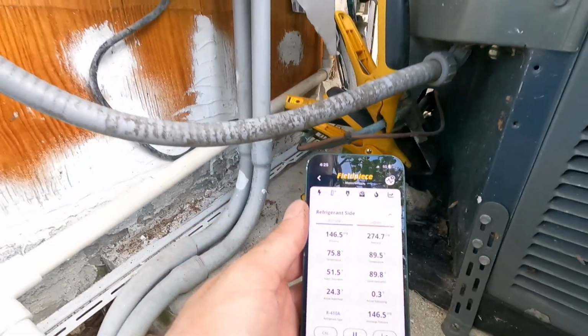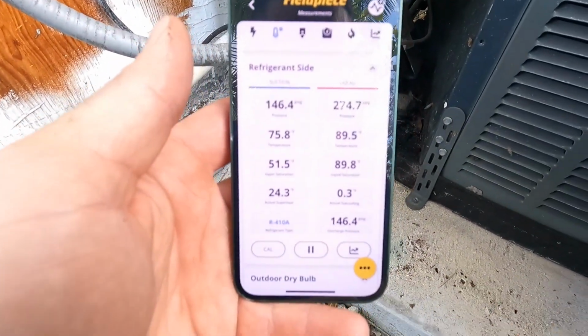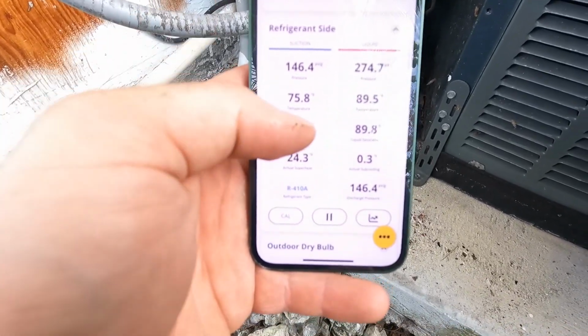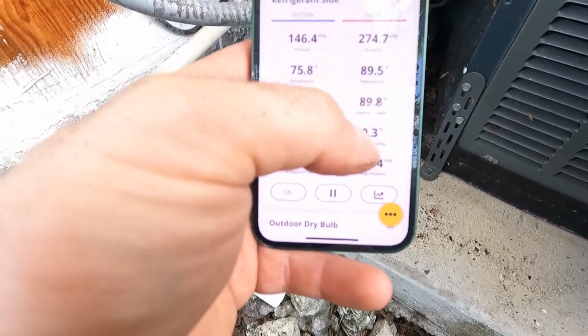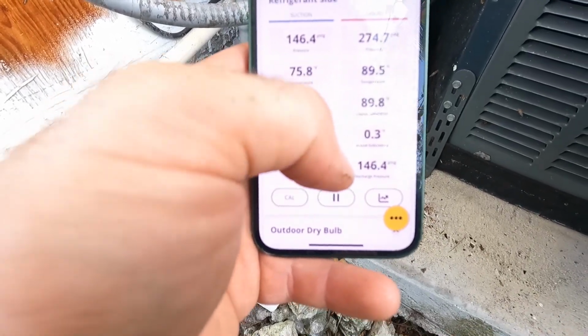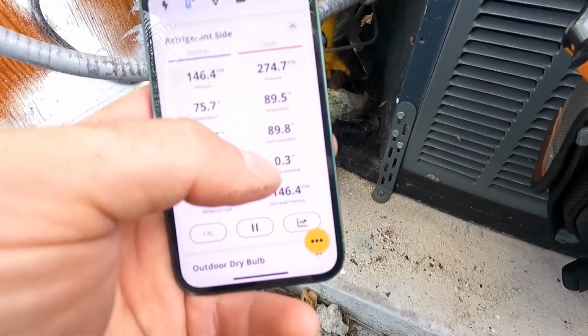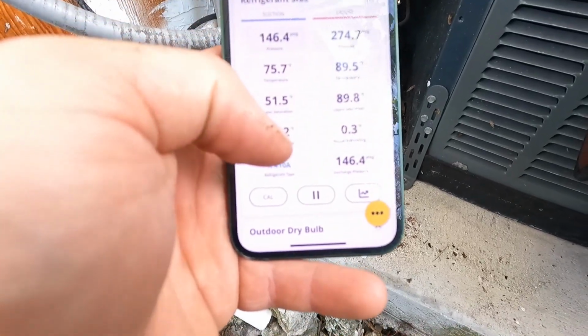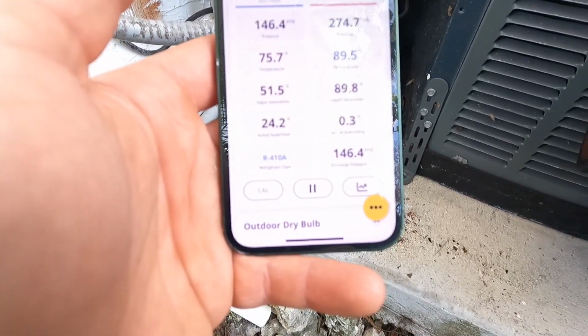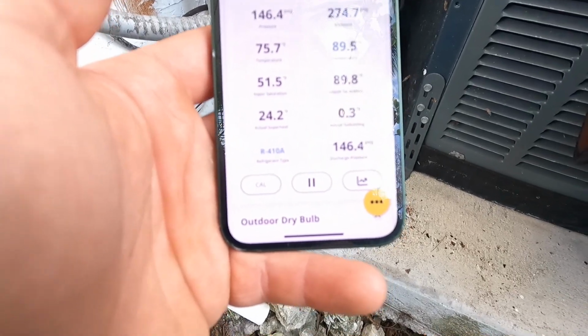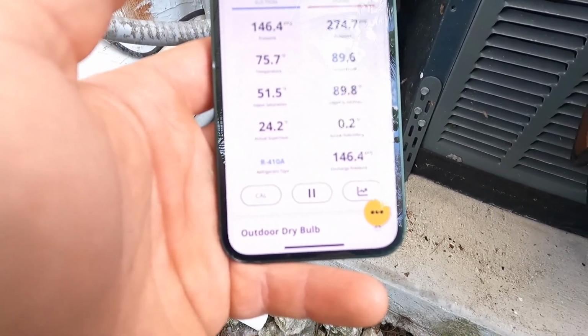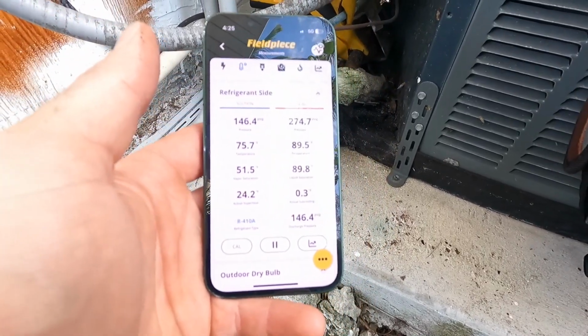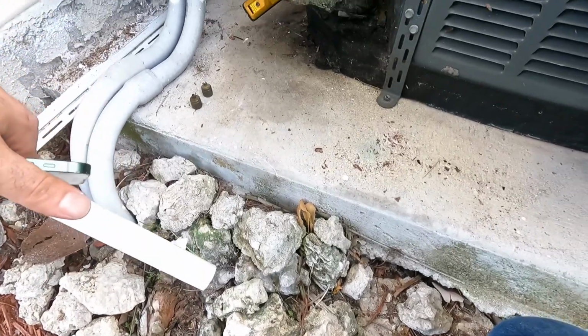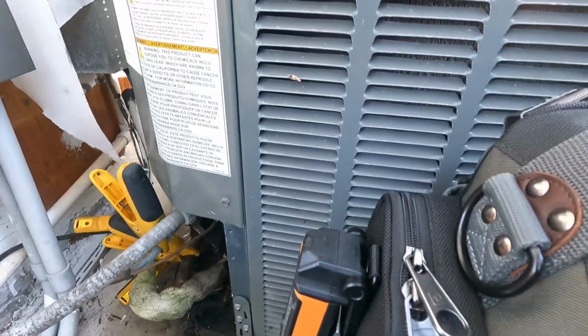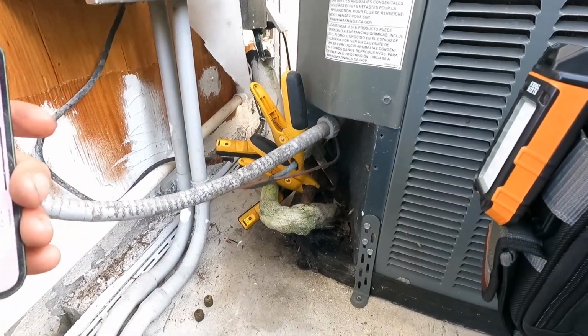Alright, 146, 51 degree saturation. Again, low subcool, but heat load outside is low, and probably could use a really good cleaning. Superheat's 24, it's a bit high, but I'm sure the heat load inside is on the higher side as well. Overall, it's cooling, not draining yet, but from the looks of that coil, it probably needs a good maintenance.